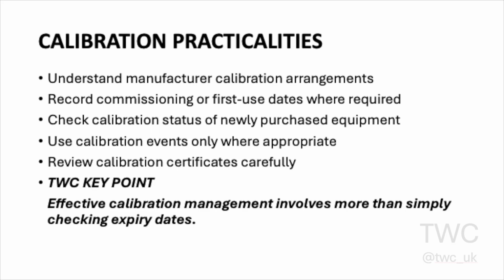Calibration management is not always as straightforward as checking an expiry date. Installers should understand the calibration arrangements used by the equipment manufacturer. Some manufacturers provide calibration certificates with new instruments and may require the user to record a commissioning date or first use date. Future calibration intervals may then be based upon that date rather than the purchase date.